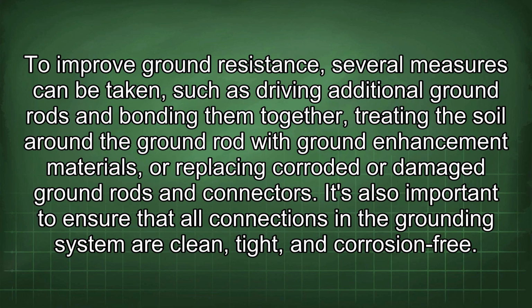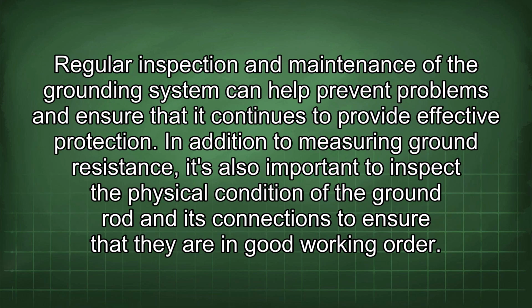To improve ground resistance, several measures can be taken, such as driving additional ground rods and bonding them together, treating the soil around the ground rod with ground enhancement materials, or replacing corroded or damaged ground rods and connectors. It's also important to ensure that all connections in the grounding system are clean, tight, and corrosion-free.